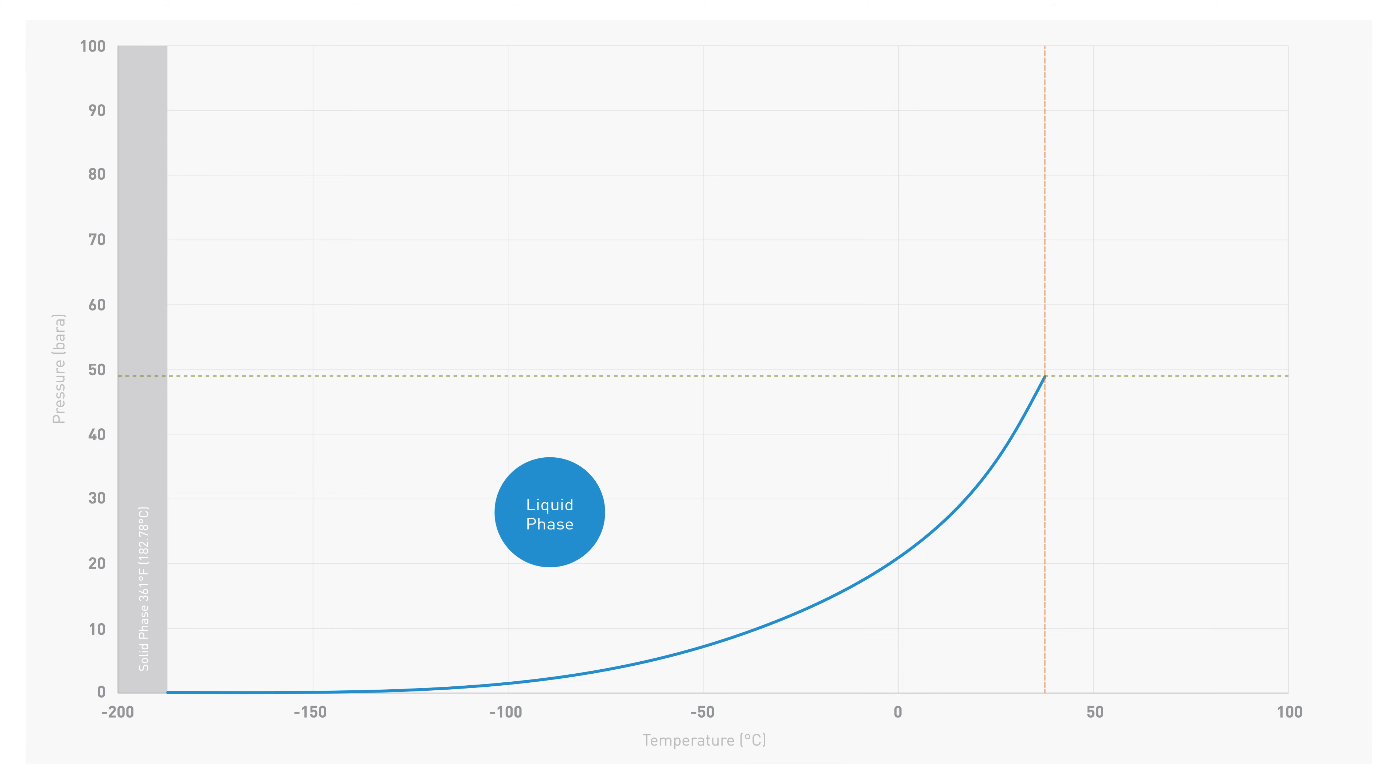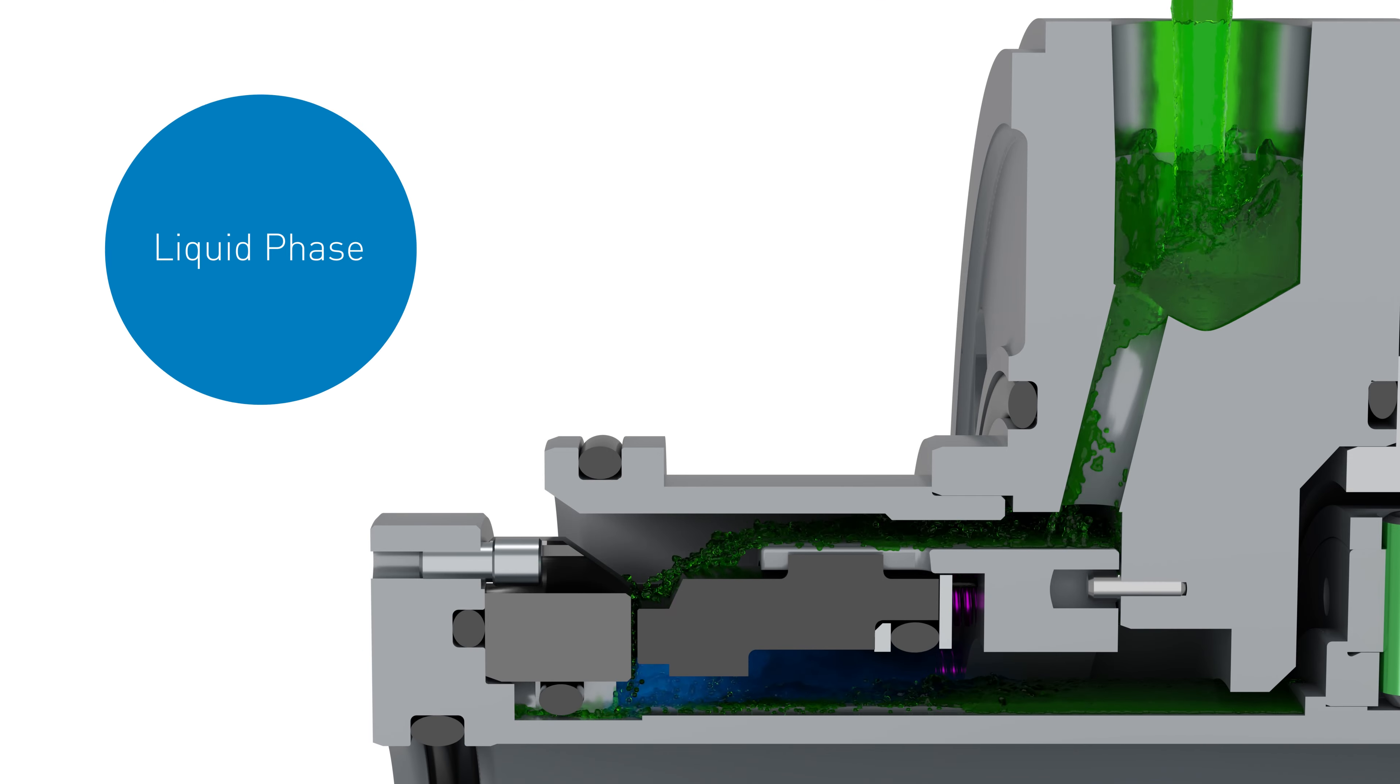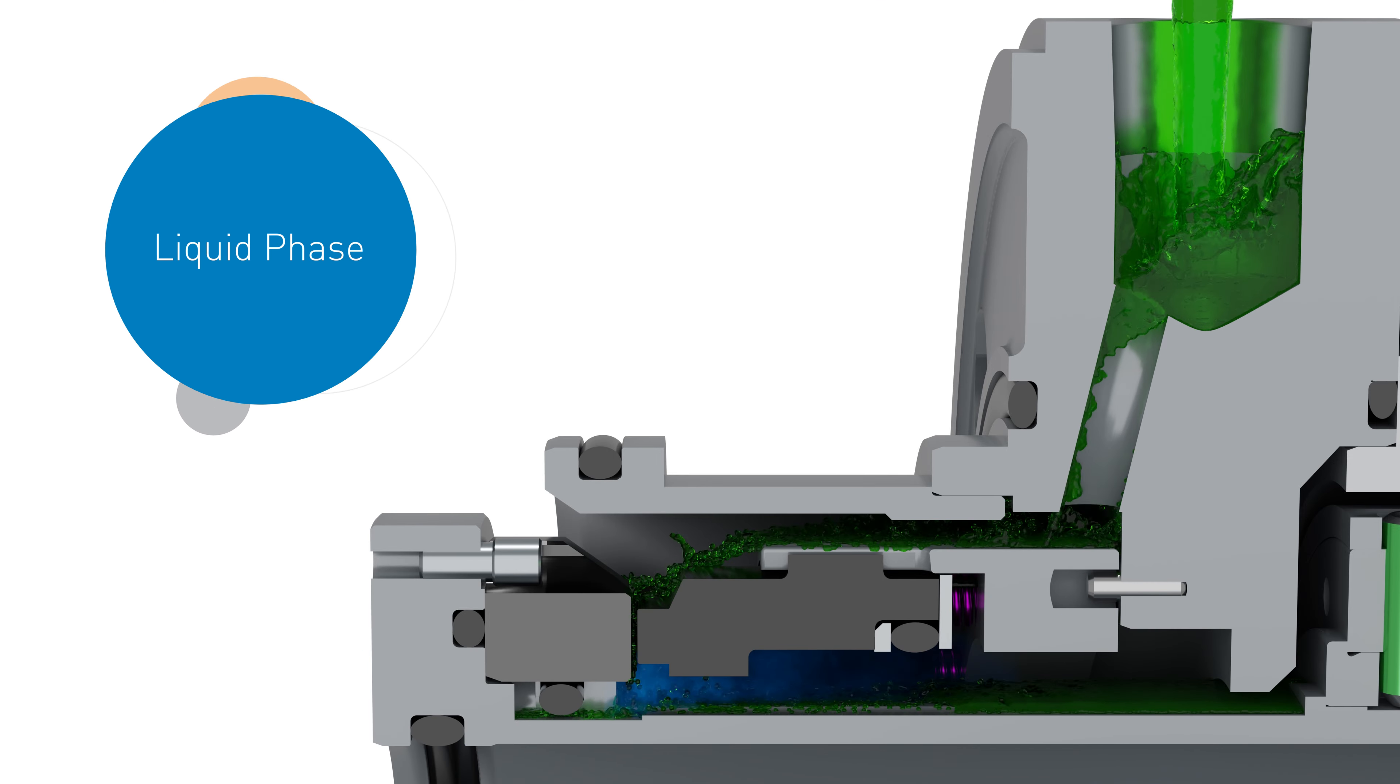If the temperature of the ethane rises above 89°F (32°C), the liquid on the seal face flashes to a vapor, which results in a loss of lubrication.